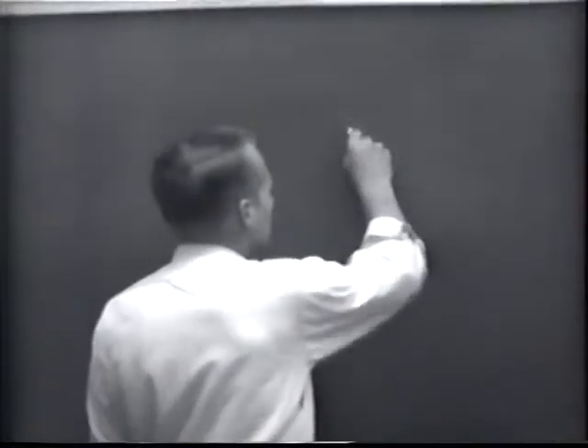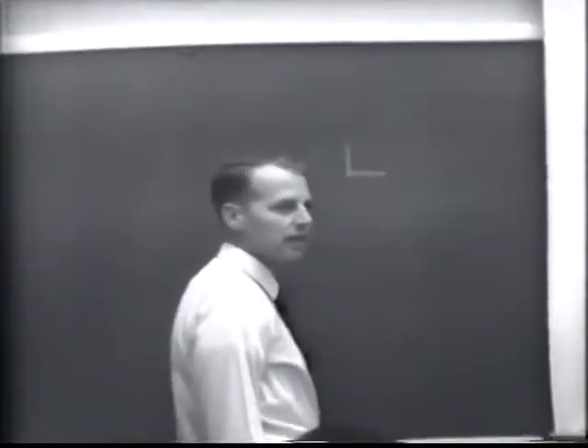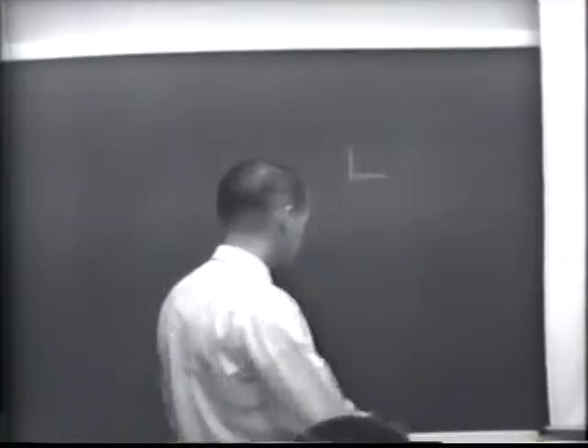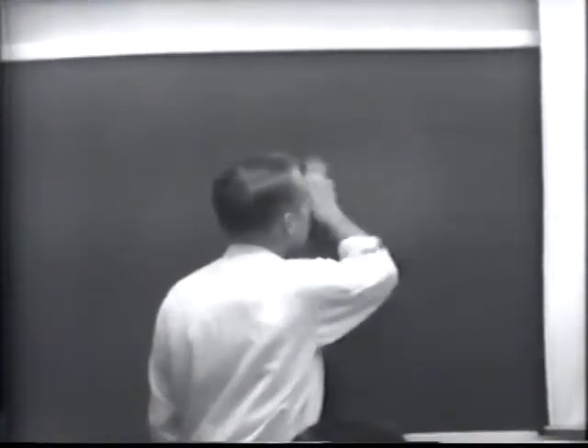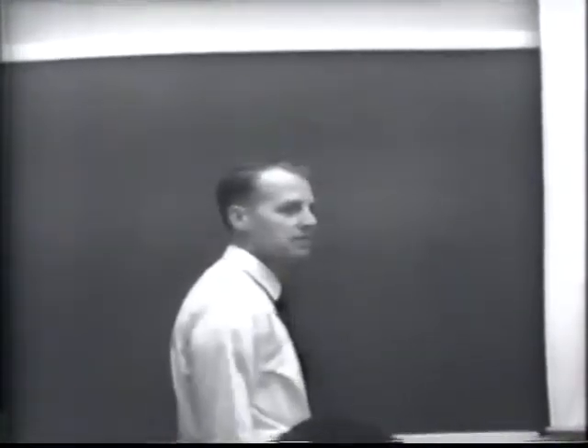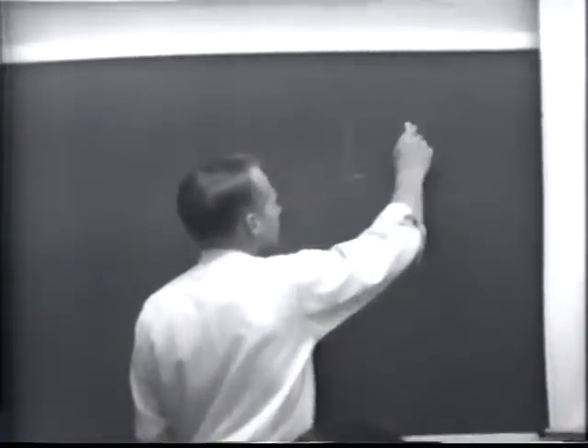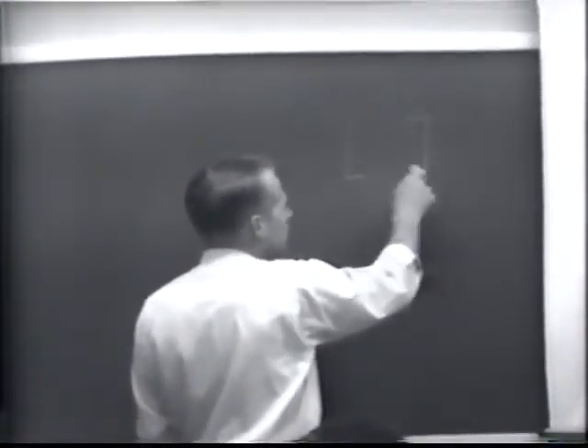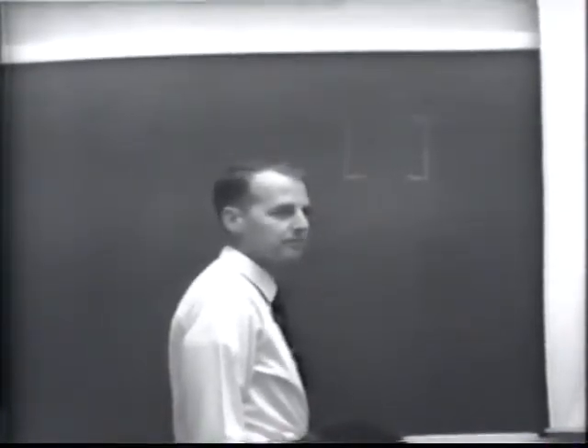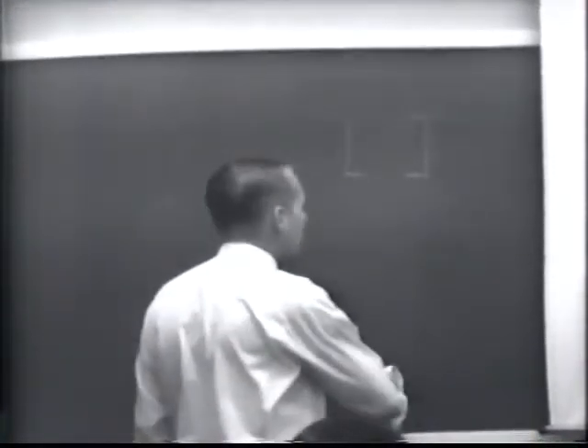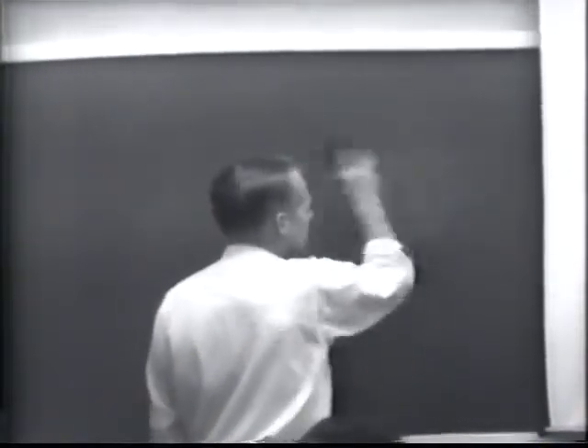And we also have some special shapes that in certain cases have been used as bus conductors. I don't know that we have any specific examples, but in some cases we have aluminum angles. Aluminum being a conductor we could use as a bus conductor. And at the higher, extremely high current levels, say in the 4, 5, and 6,000 amps, we quite often use a channel bus, which these would be channels made out of aluminum or copper, because we get better strength, better current carrying capacity on those special bus shapes.